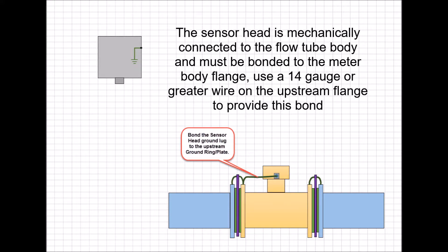The sensor head is mechanically connected to the flow tube body and must be bonded to the meter body flange. Use a 14 gauge or greater wire on the upstream flange to provide this bond.